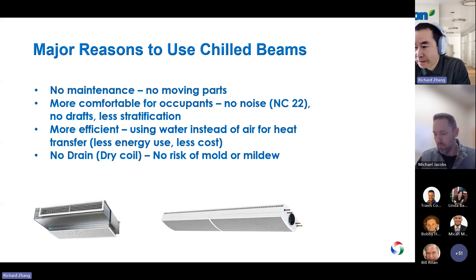On the other hand, I'm going to spend another slide regarding efficiency, so I'm not going to talk about that now. But the other reason is there's no drain, because the chilled beam is designed as dry equipment. The DOAS system will take care of all the latent load, and the chilled beam will only take on the sensible load. As a result, the coil is always dry - there's no risk of mold or mildew.